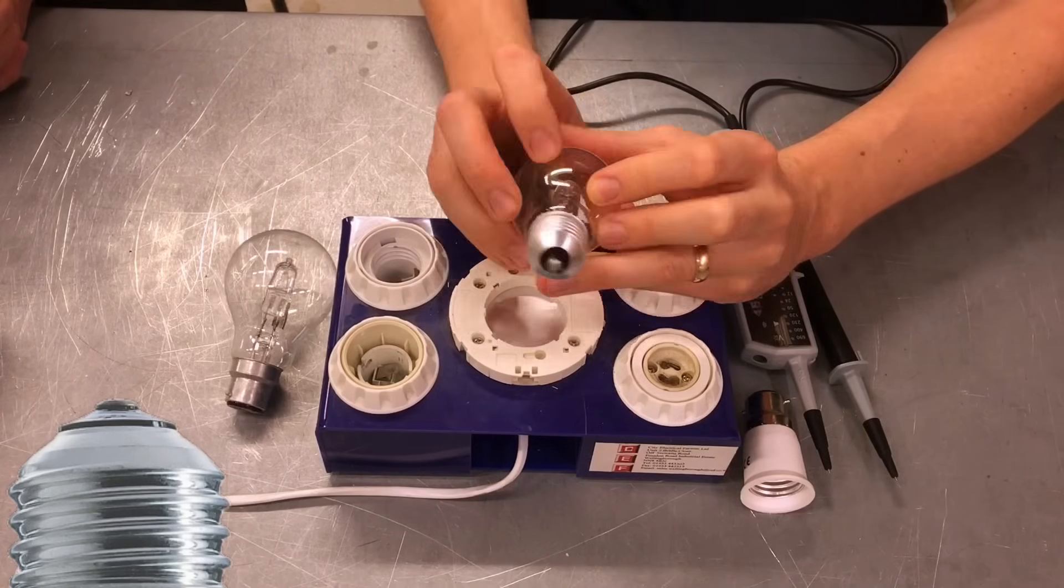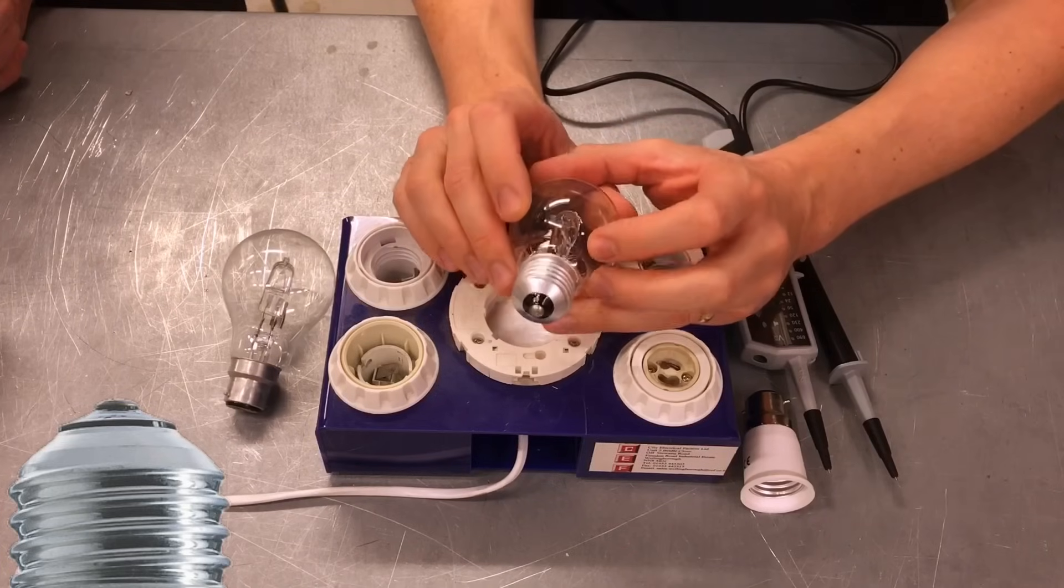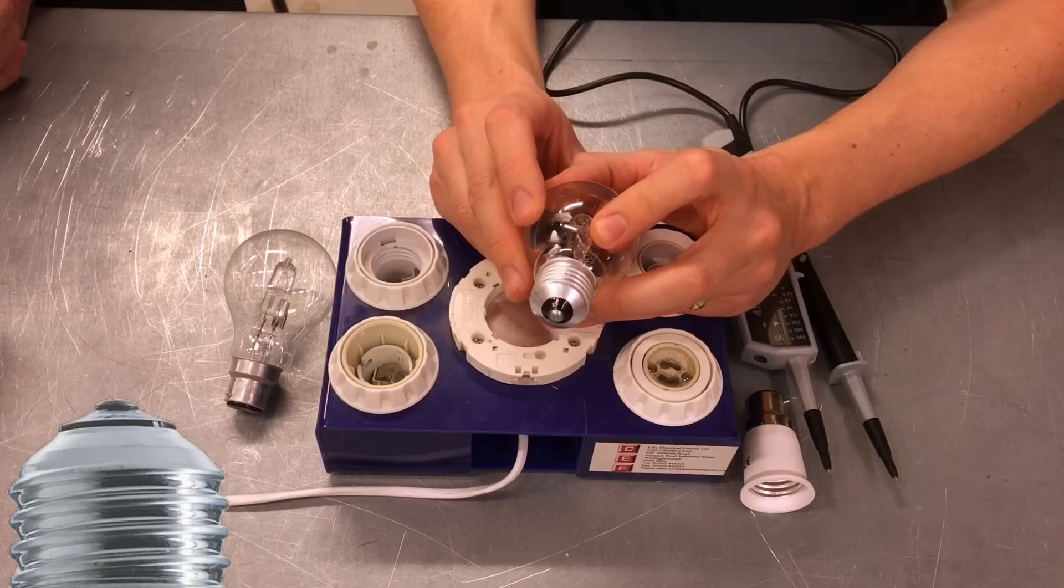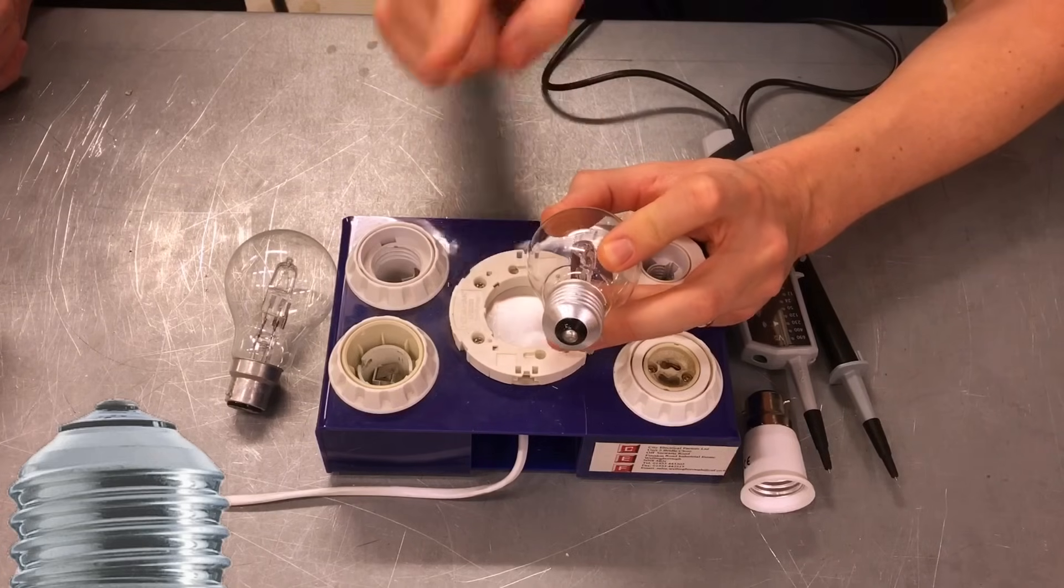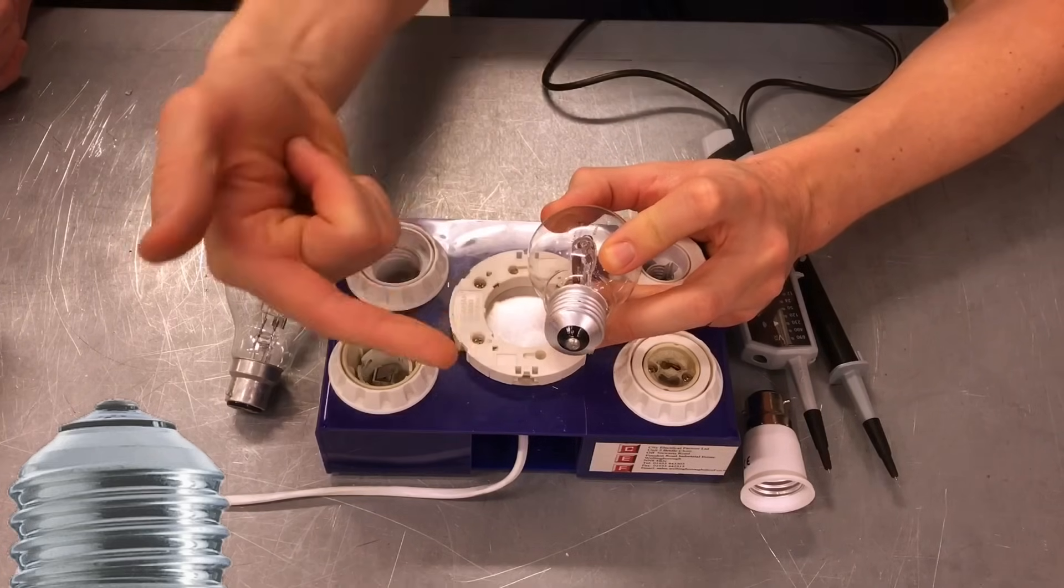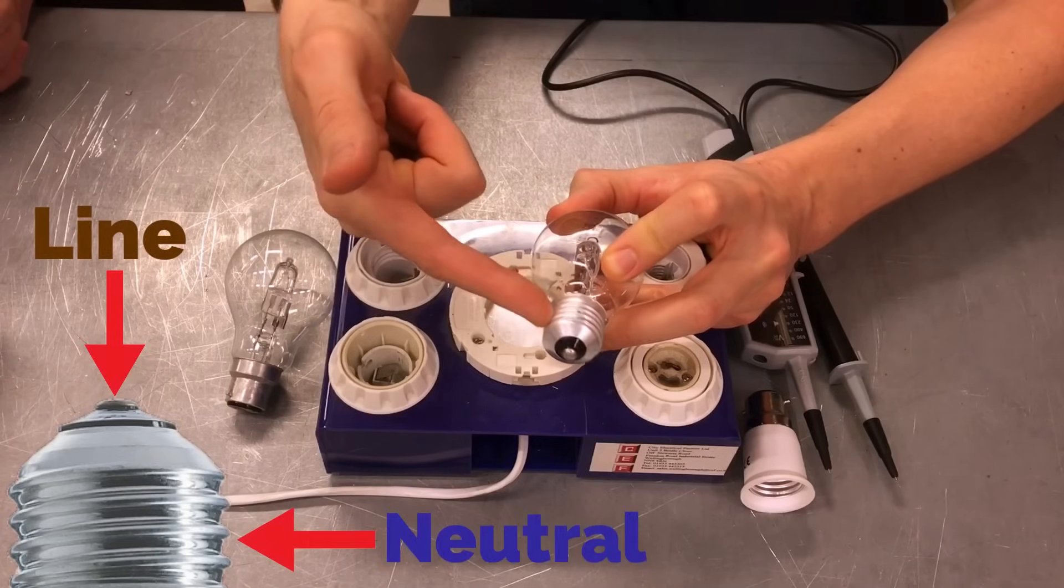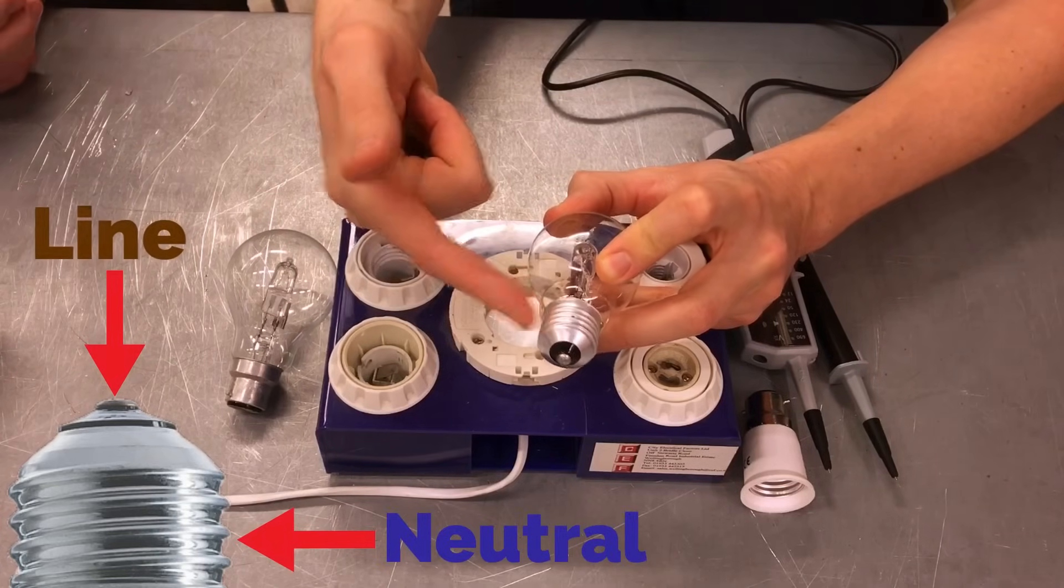Now, the issue with this is that in BS-7671, it makes it very clear that polarity testing must be carried out to make sure that when you've installed your lamp holder, this pin is the line conductor and this screw connection is the neutral.